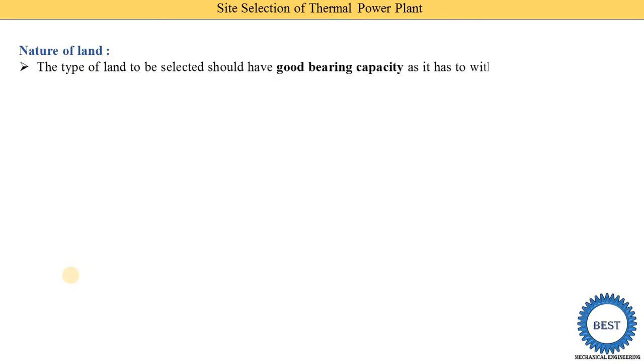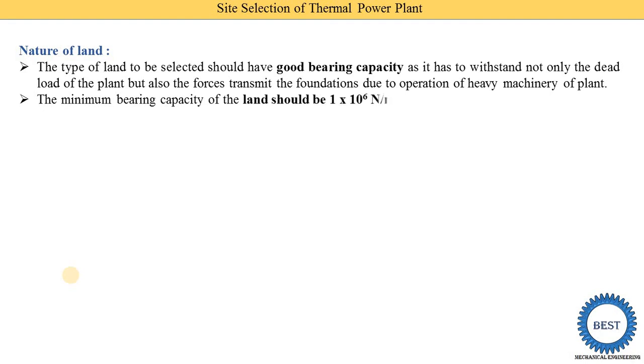Next point is the nature of land. The type of land selected should have good bearing capacity, as it has to withstand not only the dead load of the plant but also the forces transmitted to the foundations due to the operation of heavy machinery — meaning the land shall be able to sustain dynamic forces. The minimum bearing capacity of the land shall be 1×10⁶ Newton per meter square.